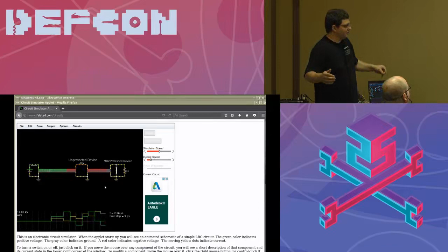It's reflecting the surge back onto the other device. And you see the unprotected device went from 10 kilovolts to 19 kilovolts. It actually amplified the surge. So this can happen, it happens on very short time scales. It may not matter, but if you have surge protectors or whatnot, you should have them on every device so that you don't get these potential reflections hitting your other devices.